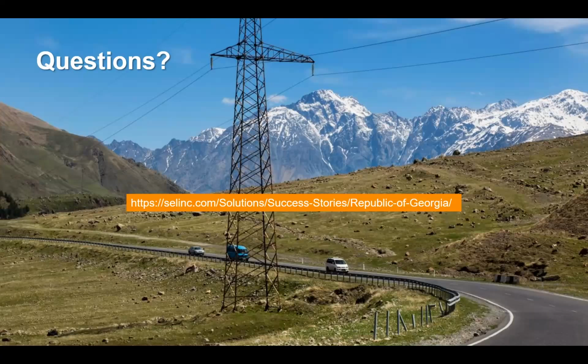60 milliseconds. 60 milliseconds from detection of the contingency to the control actions issued by the end device, let's say. It takes about 60 milliseconds. Okay. 60. Got it. Very fast. Yes. And everything is based on GOOSE messaging. We do not use IEEE C37.94, which is preferable for other vendors. We would like to welcome everybody in Georgia and see how this system has been operating for many years, based on GOOSE messaging. Yeah. Great.